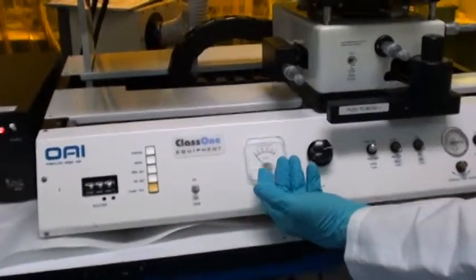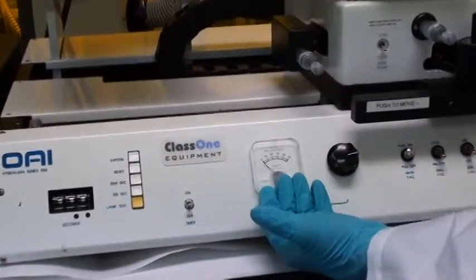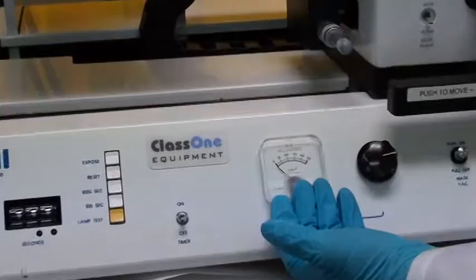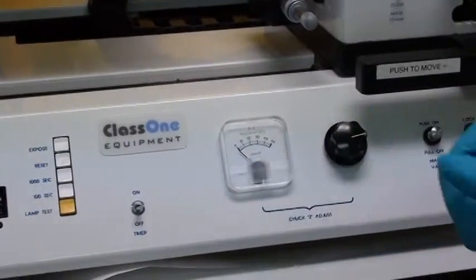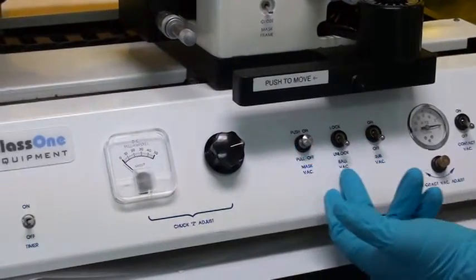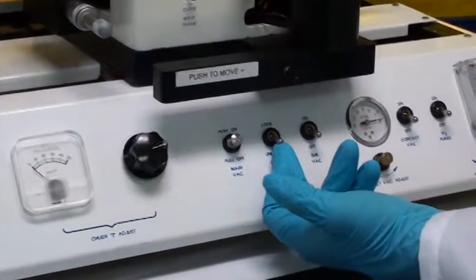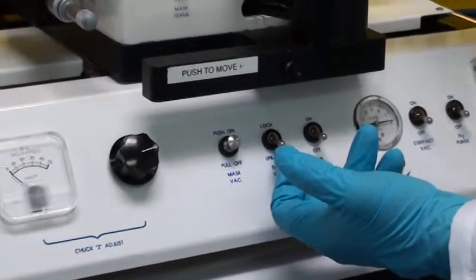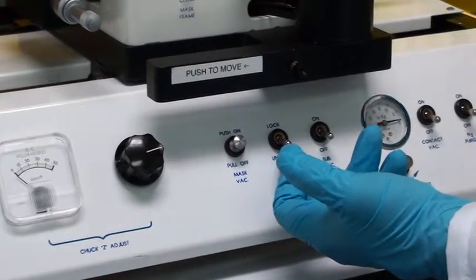This is our chuck Z adjust for leveling the wafer, which we'll get into in a minute. Here is your mask vacuum to hold your mask onto your mask holder. Next is what we call our ball lock, which will lock our wafer to the proper level.